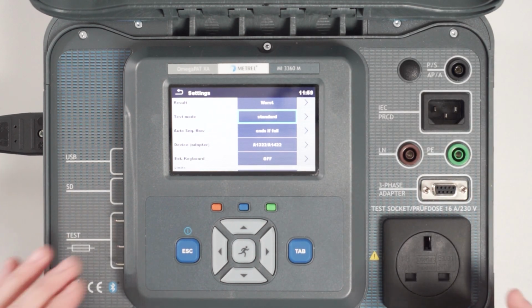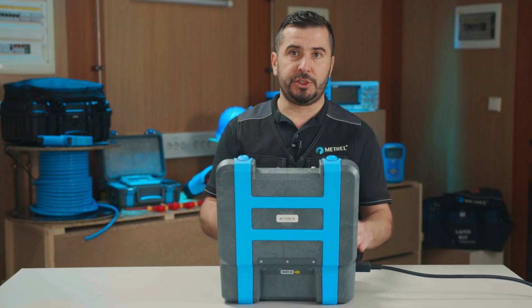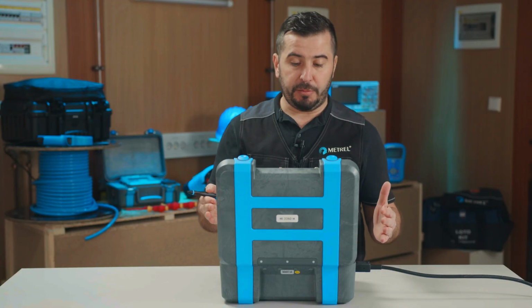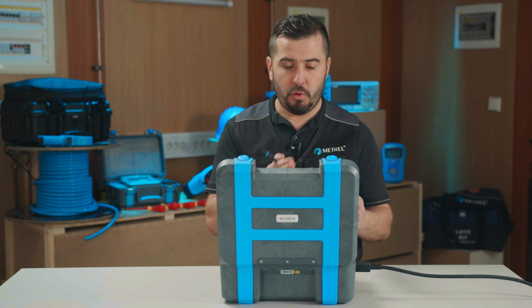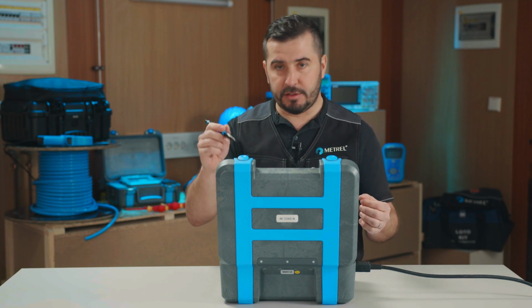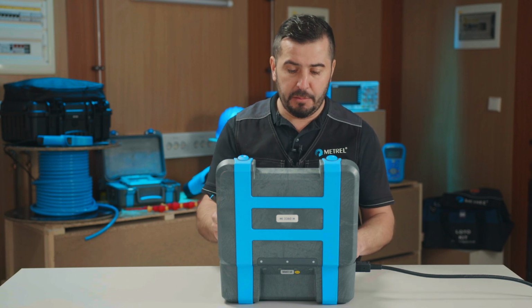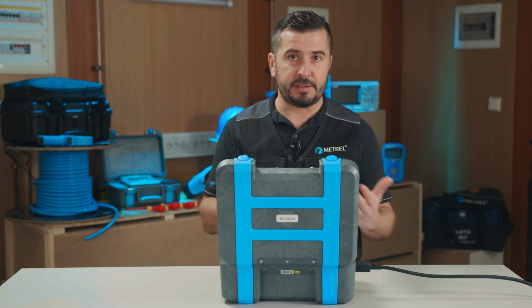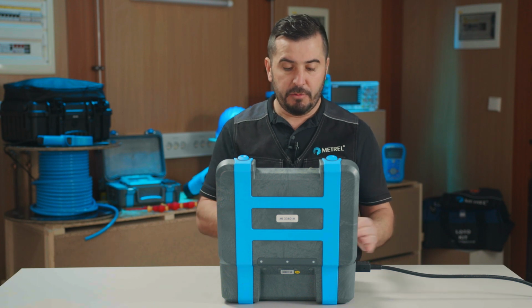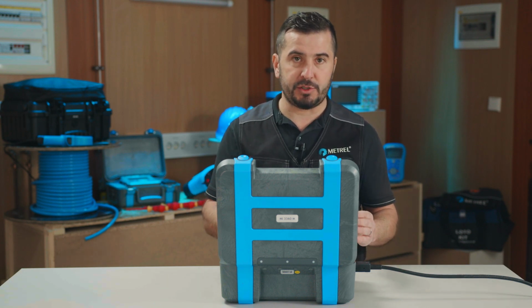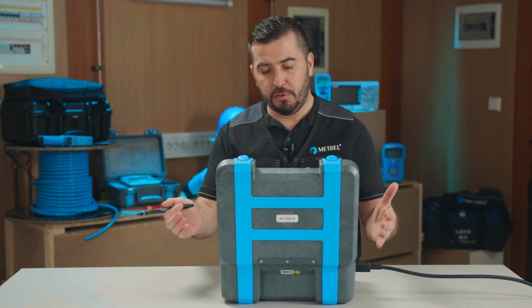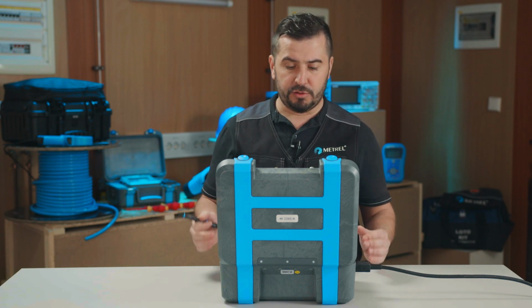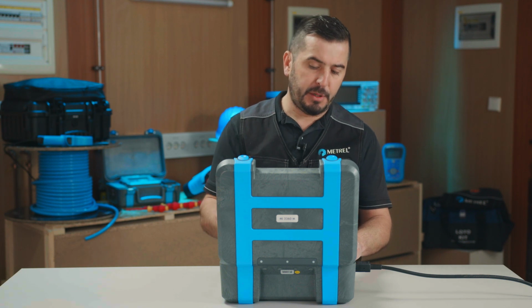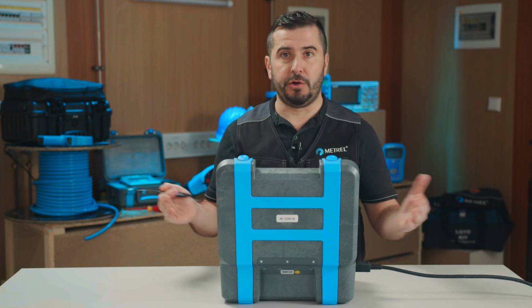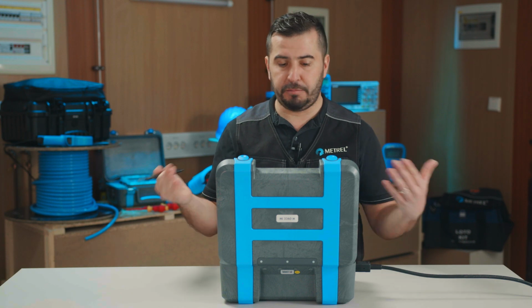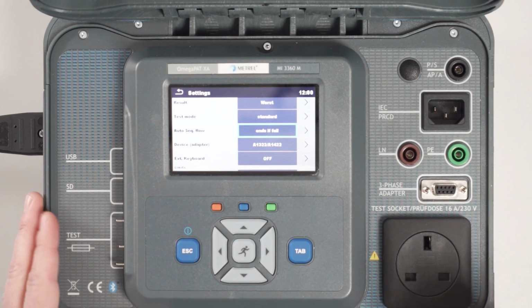By default it is set to ends if fail, which is correct, because each appliance has to pass all measuring steps to be considered and validated as passed. But for troubleshooting, for example, inside service departments, etc., when we have to repeat some measuring steps or determine whether we have removed the error or not, we can also set it to proceed if fail. But be sure that if you are testing portable appliances periodically, that it is set to ends if fail.